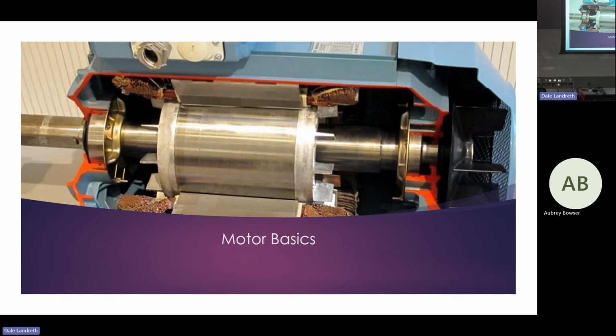It says because the conductor resistance is so low. So on a three-phase motor, what do we think the conductor resistance is? On a CVHE 1,000-ton chiller, what do you think the resistance is, if you were to ohm it out? Say it's 100 ohms? Not that much. Anybody know? I asked this last time. 2 ohms? It's going to be something like that, pretty low.